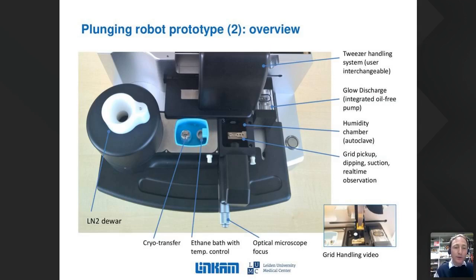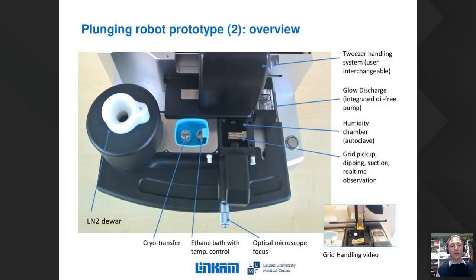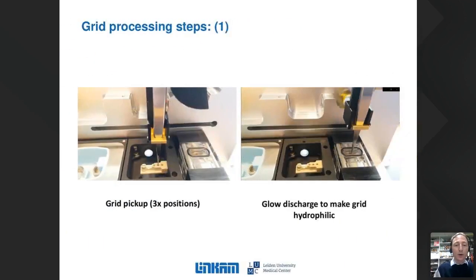Looking at the different components: on the left in blue is the cryo compartment and the small container for plunging. On the right-hand side is the glow discharge unit, the pickup locations, observation and film thickness adjustment position, and sample dipping. The micrometer at the front is the built-in microscope to allow real-time monitoring. On the left you can see the automatic grid pickup where you place the sample grid ready for processing.